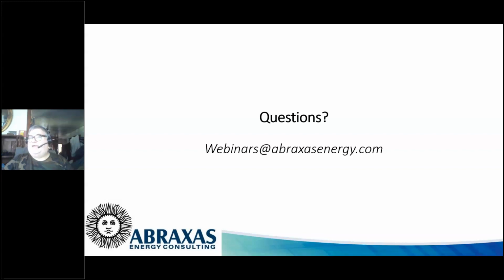You operate on that. How do you go about finding pump curve data, especially for existing buildings with limited information? Well, that's a good question, because that third example had you got a nameplate. It's supposed to have a nameplate on the pump that gives you fundamental flow and feet. Okay, that's fundamental. Sometimes they'll put the pump impeller size on there, but the manufacturer keeps track of just about every job they sell, and you would end up having to go back to the manufacturer if you can get a good number off of that.